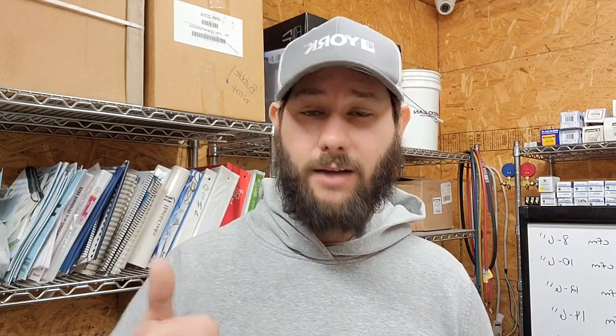So we have to make modifications to the ductwork so that it'll actually work properly, especially for a heat pump. You have longevity if you have the right duct size. If you don't have the right duct size, the life of your equipment is shortened, cut in half, and you have lots of issues, and we want to avoid all those issues.